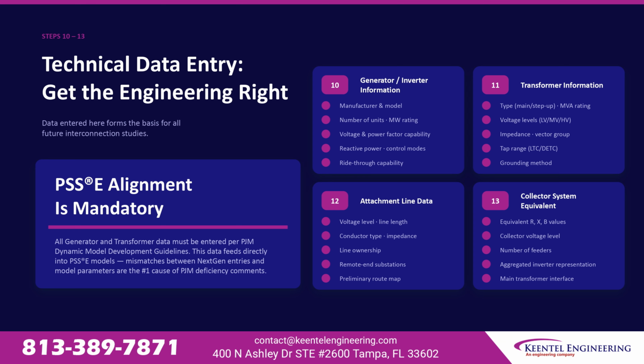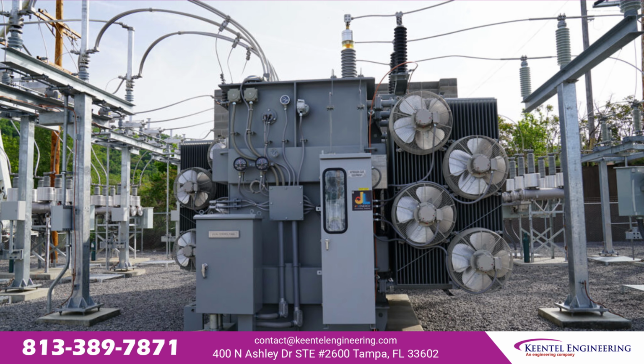Provide equivalent R, X, and B values, collector voltage, number of feeders, aggregated inverter representation, and main transformer interface. PSS E alignment is mandatory. Mismatches between NextGen entries and your dynamic model parameters are the number one cause of PJM deficiency comments.